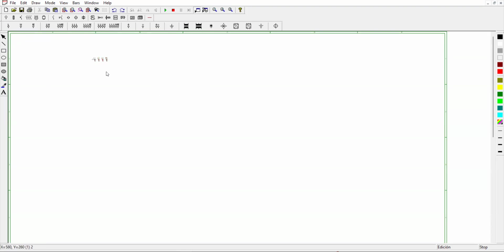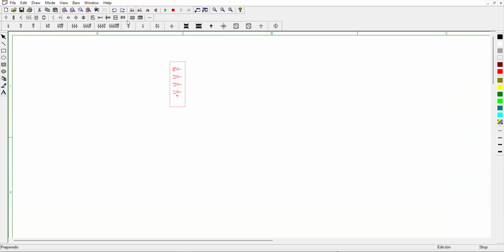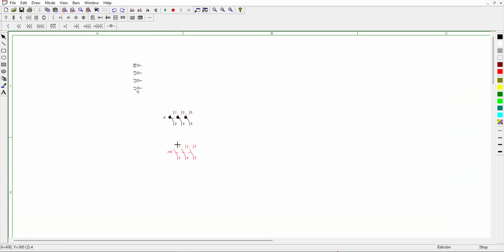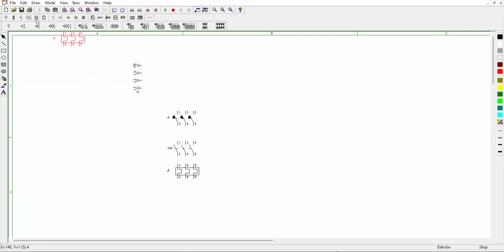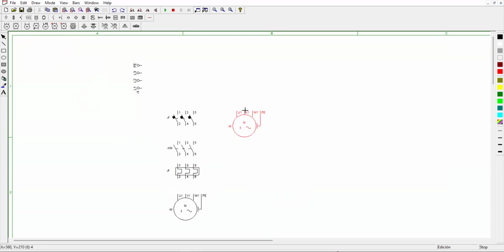So we need a power source here. Of course, we need a three-phase circuit breaker, three pole, and a magnetic contactor. We also need a thermal overload for our magnetic contactor, a three-phase motor, and at the same time, we need an additional two-pole circuit breaker for our control circuit diagram.